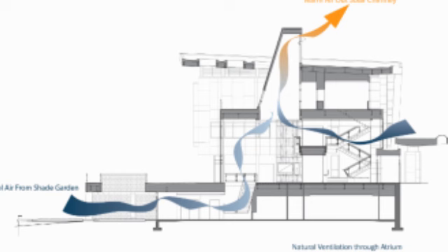Ventilation should be considered for its relationship to venting for appliances and combustion equipment such as water heaters, furnaces, boilers, and wood stoves. Most importantly, the design of building ventilation must be careful to avoid the backdraft of combustion products from naturally vented appliances into the occupied space.